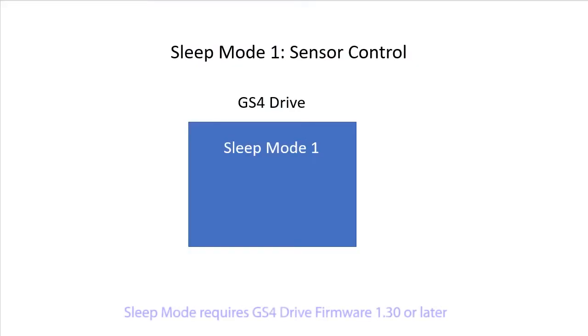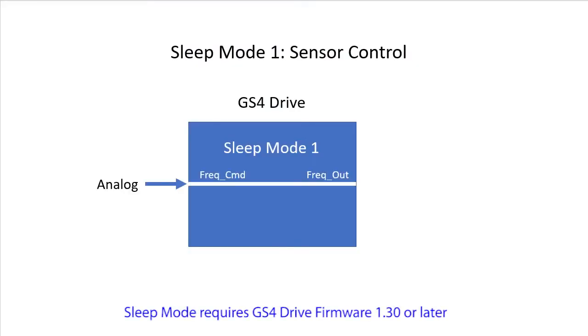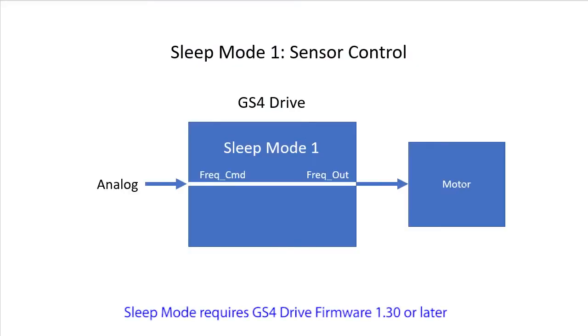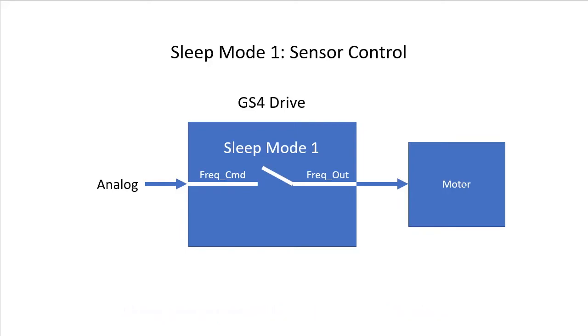Sleep Mode 1 uses the sensor feedback to directly control the drive's output frequency. Sleep Mode watches that value and when it reaches a limit you set, it turns the output frequency to the motor off.